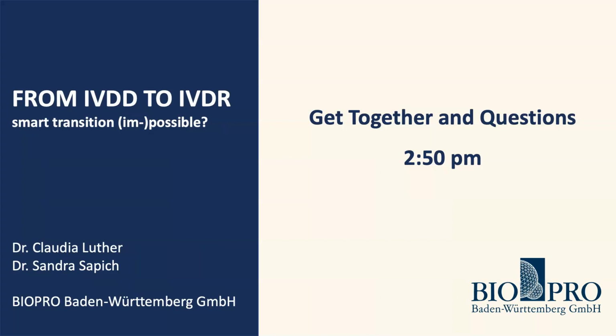No, it's not. So in accordance with what is documented in the regulation, the technical file, so if you are the legal manufacturer, let's start from that point. You are the legal manufacturer, but you are the virtual manufacturer. You don't have ideas of the design of the product. You don't know how to manufacture the product, but you have very good partners doing that for you under corresponding contractual agreements.